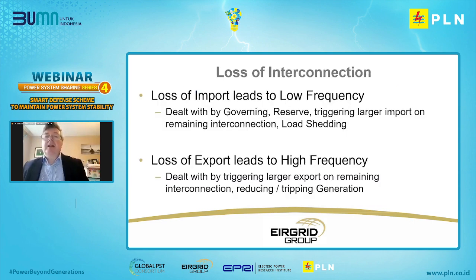So I suppose the challenges here. If we lose interconnector import, we're left with a deficit of power on the island. That leads to low frequency. That's dealt with by the normal governing reserve and maybe tripping load or load shedding if we need to do it. I suppose the new problem we have with interconnection is the loss of exports leading to high frequency. This is dealt with by reducing or tripping generation, so it depends on the circumstances. This can be wind generation or a conventional plant. So next slide, please.